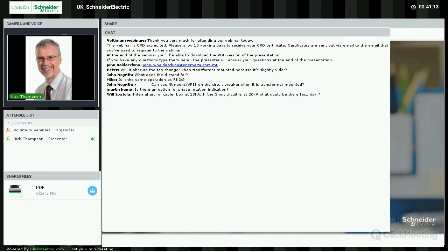Short circuit at 20 kA. The internal arc rating of the cable boxes has been tested at 13 kA. Obviously, the fault studies would have to be done by an appropriately qualified person to determine what the fault level would be at that particular point. For short circuit, this is current withstand. It's still rated at 21 kA, short circuit, short time withstand at 3 seconds, so that shouldn't affect the risk. Thank you very much indeed.